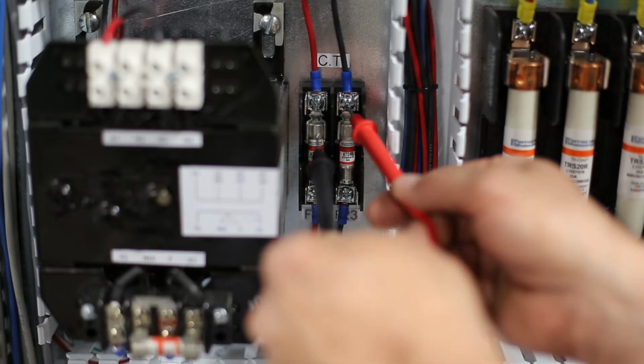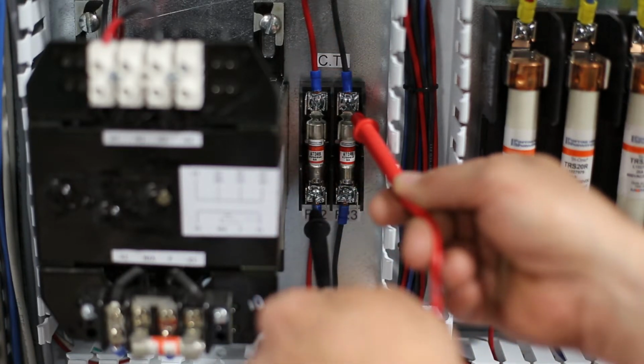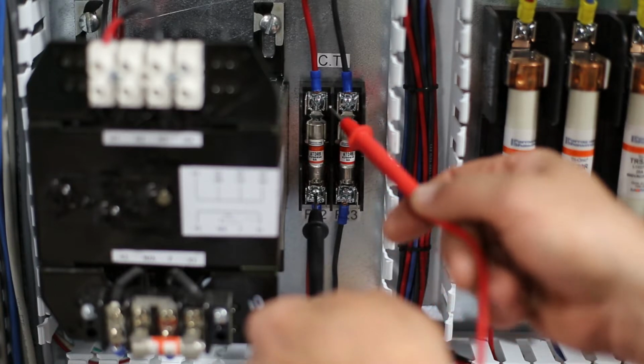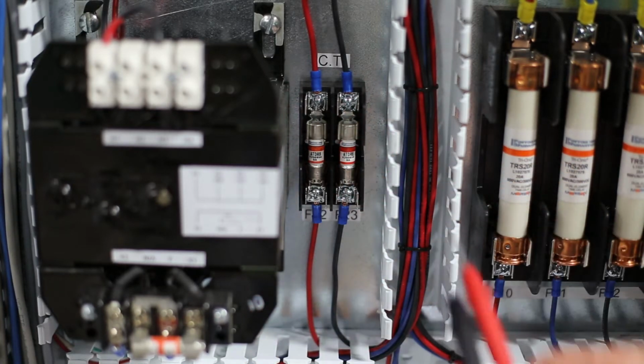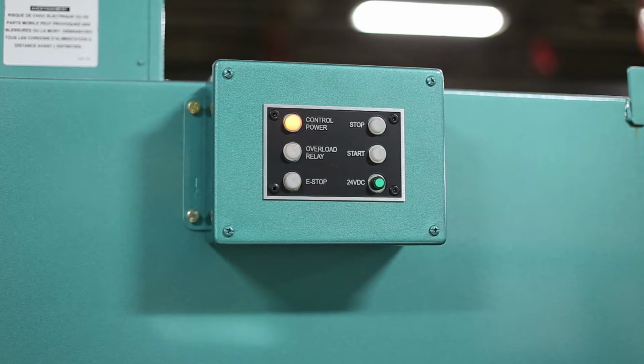If you don't, that fuse on number 2 is bad. And then once we verify that, you go to the top of the second one to the bottom of the first one. If you do not have 240 volts, that means fuse number 1 is bad. As you can see right now, we only have control power. So at this point, we need to go verify our control transformer to see where our problem is.